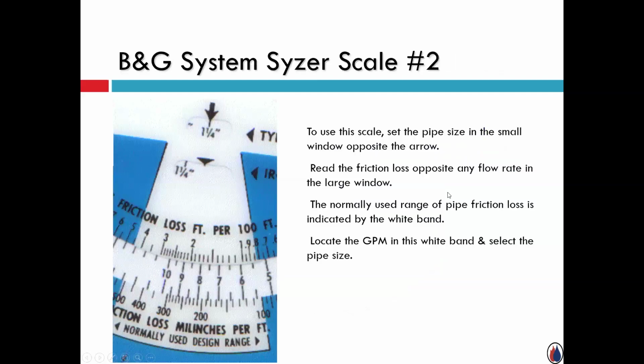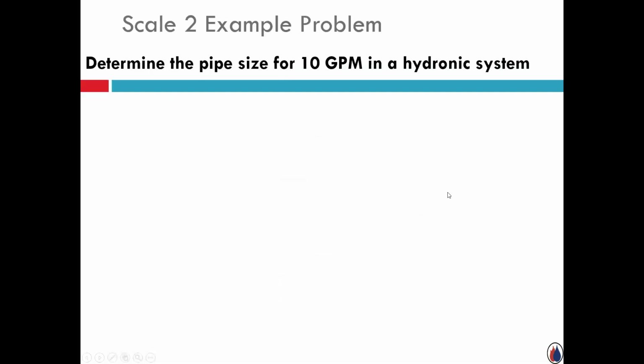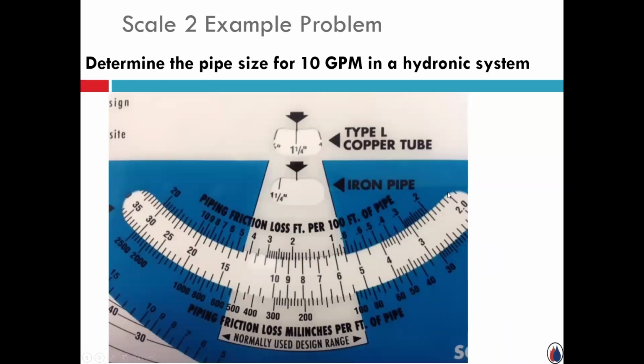Anyways, it's just an enlarged view of it, if you will. Again, pretty low numbers, but they actually kind of correlate to what we just figured out on Scale 1 with some flow rates. In this case, this example is saying, determine the pipe size for 10 gallons a minute in a hydronic system. So the way I approach it, or the way you would use the wheel if you so chose to use it, is you'd be down on Scale 2, and in this white band, I want to try to find the flow rate that we're looking for. So in this example, we're saying 10 gallons a minute is right here, somewhere in that white band.